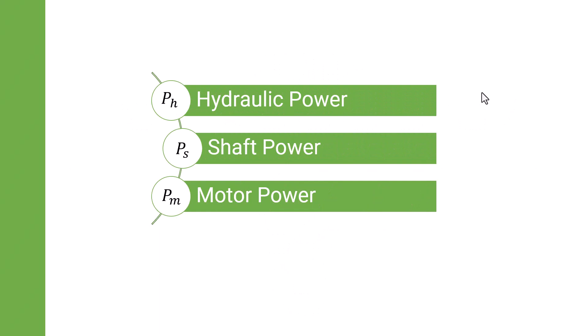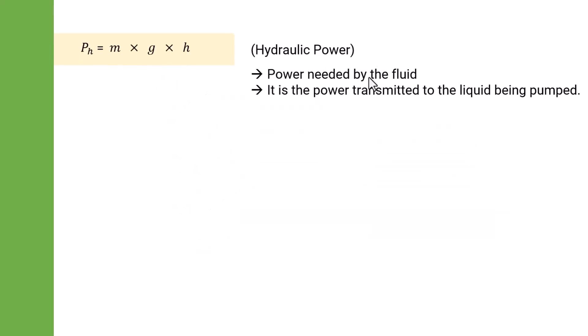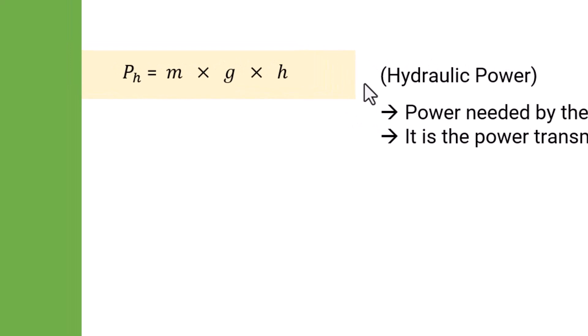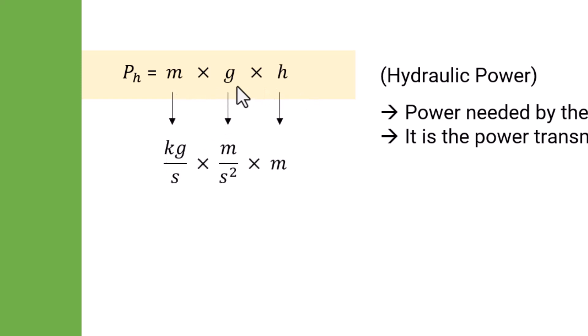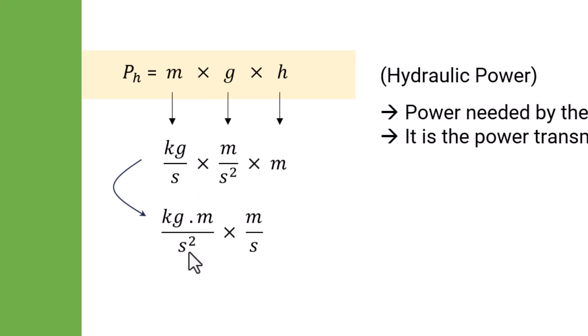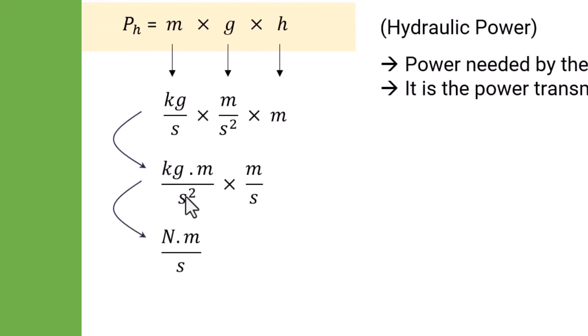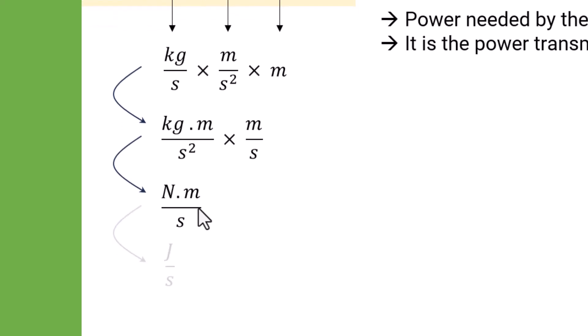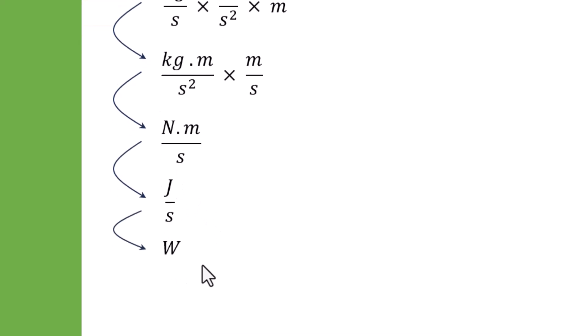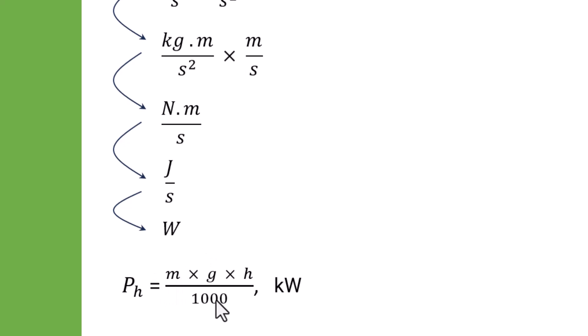In pump power calculation I will cover three different formulas: hydraulic power, shaft power, and motor power. Hydraulic power is the power transmitted to the liquid being pumped. The formula is very simple: it is mgh, where m is the mass flow rate in kg per second, g is the acceleration due to gravity in meters per second squared, and h is the differential head in meters. Rearranging units: kg·m/s² × m/s gives newtons × meters per second, which is joules per second, which is watts. Dividing by 1000 gives kilowatts.